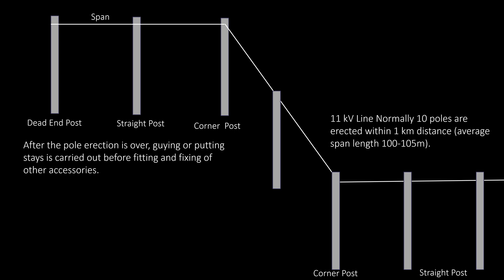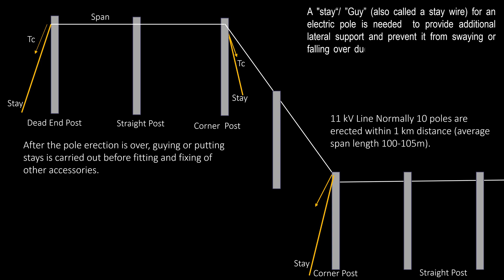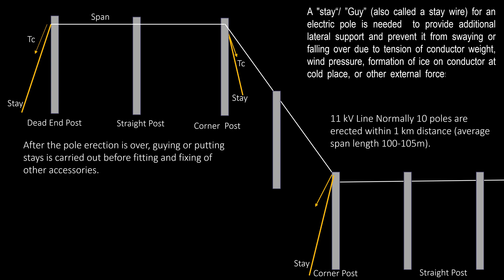In the picture, we see some poles are positioned on a straight line and a few are on a corner to match the route of the line, and the yellow line shows the position of stays of the poles. A stay or guy, also called stay wire, for an electric pole is needed to provide additional lateral support and prevent it from swaying or falling over due to tension of conductor weight, wind pressure, formation of ice on conductor at cold places, or other external forces — essentially reinforcing the pole stability by counteracting unbalanced forces acting on it.